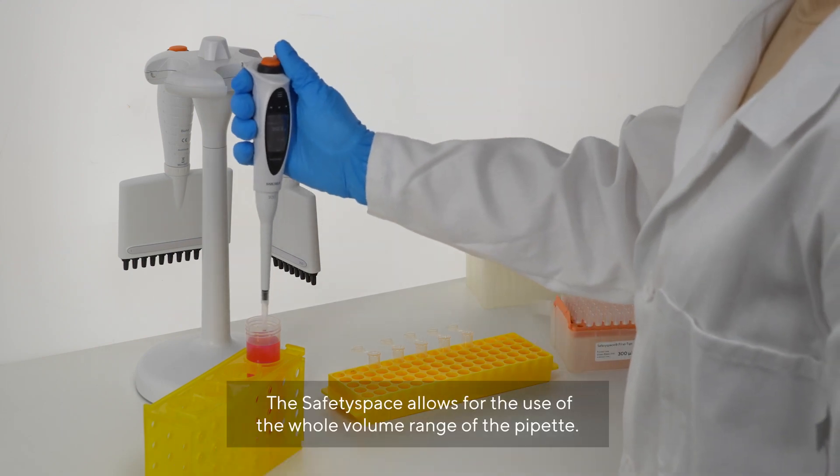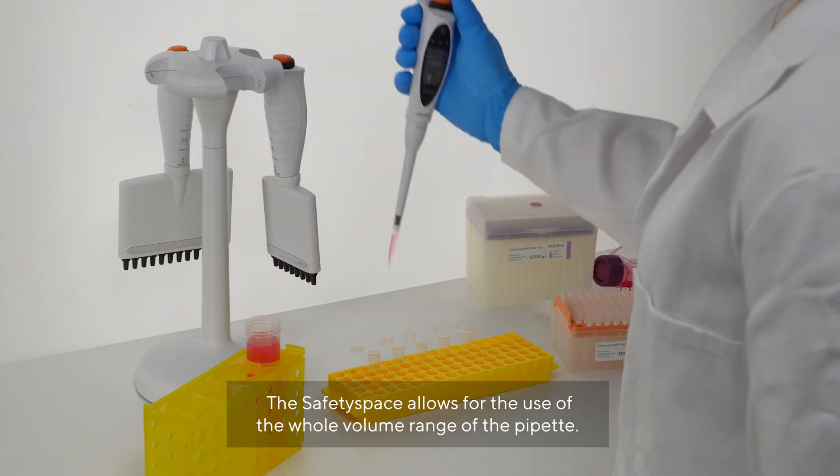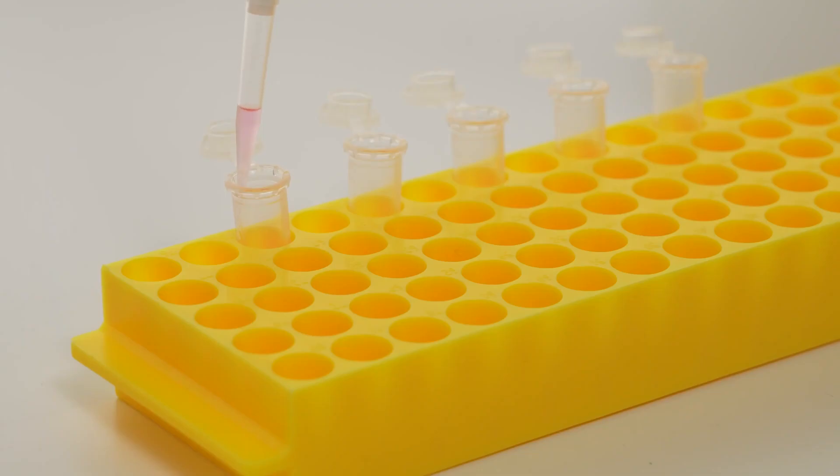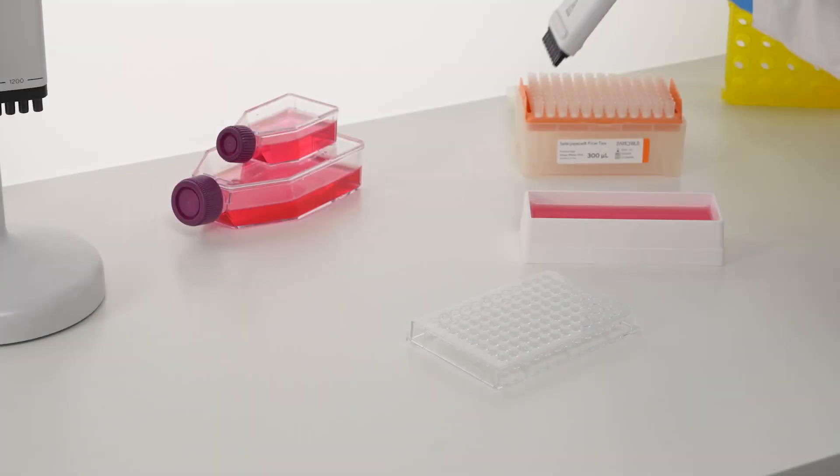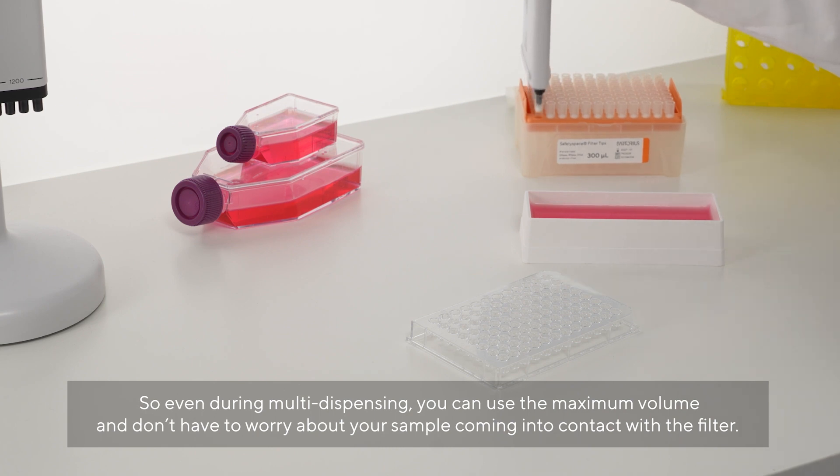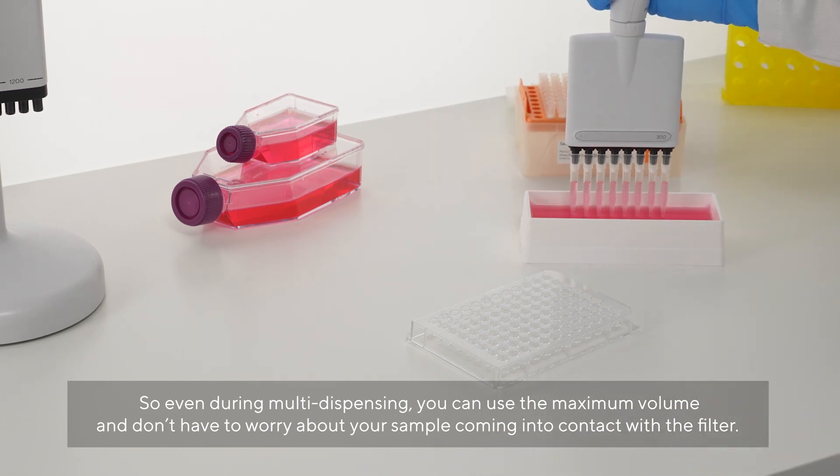Safetyspace allows for the use of the whole volume range of the pipette. So even during multi-dispensing, you can use the maximum volume and don't have to worry about your sample coming in contact with the filter.